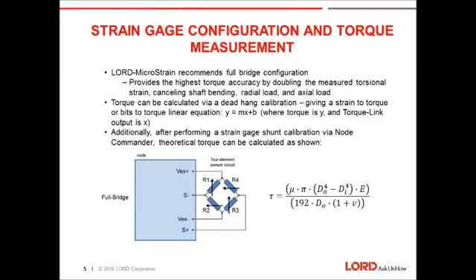First, it can be calculated via dead hang calibration, where a customer has a torque arm with a known length, and then they can hang a known weight on the torque arm to provide a known torque input, correlate that to strain. In those cases, the customer probably would want to have multiple weight increments, for instance 10, 50, and 100 pounds, depending on the length of the torque arm, to get a few different points to be able to create a linear calibration to convert the strain to torque. Then they'll be able to input that into Node Commander, assuming they use a linear calibration y equals mx plus b, and get torque directly from Node Commander.